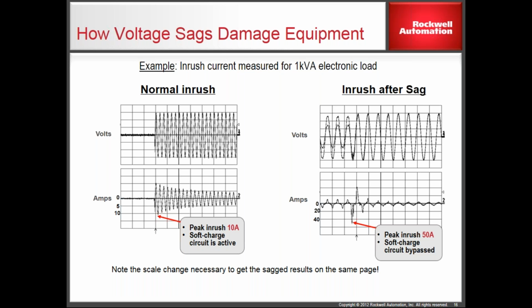Imagine what happens when that current hits, it heats up, hit with 17 times the expected current, so the diodes get hot, then they cool off. When they get hot they expand, then they cool off. It's a plastic package, they get hot and cool off repeatedly, and over the life of the unit, expanding and contracting these diodes, until finally it mechanically fails. That's why drives last a lot longer, they're a really rugged power supply compared to some others, where once is enough and those things go the first time.